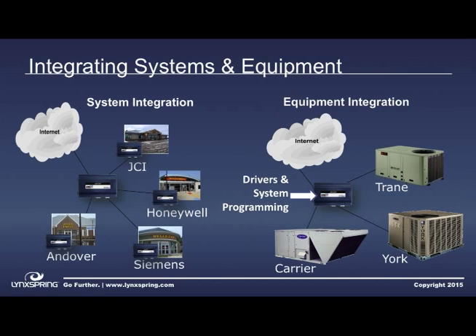As Pat alluded to, there's field devices and then there's supervisory devices. And what we normally will do is replace the supervisory devices with drivers, hardware, and of course your intellectual knowledge of programming to provide different systems commonalities. We normalize the data between, and I used all air handlers in this example. It could very easily have been outdoor lighting, could have been the lawn sprinkler system. It doesn't really matter what the equipment is, but they're different systems all brought in using a device driver in your programming into a common platform with the capabilities and extending that out through local area networks, the internet connection, third-party applications, export of data to some other location. But all of that is available when you've brought them all into a common system.